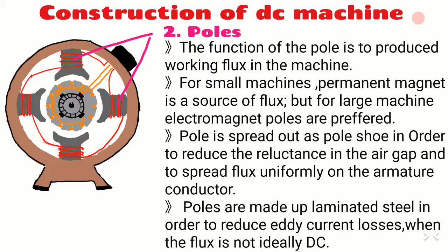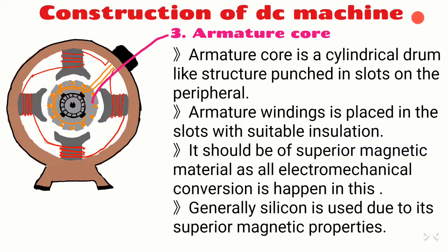The armature core is a cylindrical drum-like structure punched with slots on the peripheral. The armature winding is placed in the slots with suitable insulation. It should be of superior magnetic material, as all the electromechanical energy conversion happens in this rotating part. Silicon steel is used as it has superior magnetic properties. Due to high conductivity, solid cores would produce eddy currents, so they are not preferred; instead, cores with thin laminations of 0.4 to 1 mm thickness are used. 3.5 to 4% silicon is added to steel, which reduces iron losses in the core.